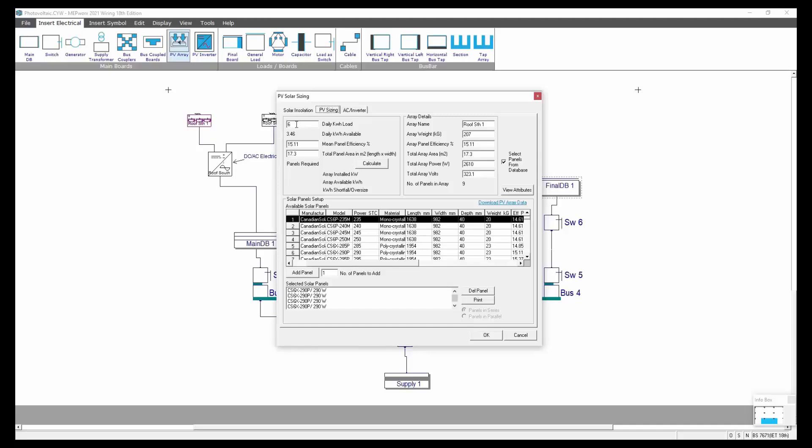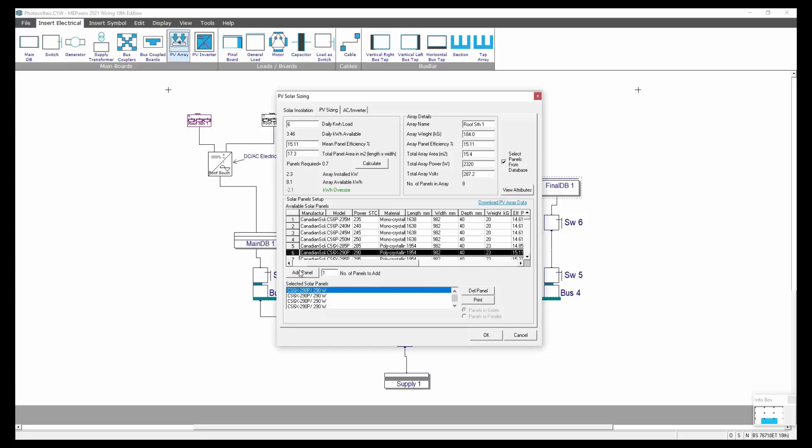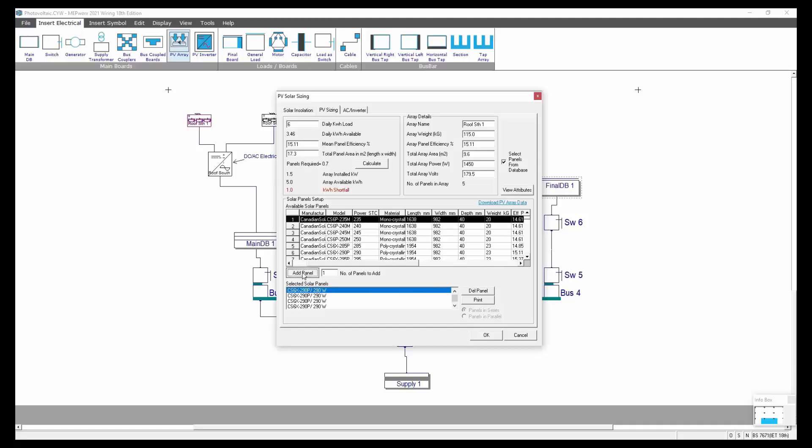When you go to the PV sizing tab, if you're servicing a daily load of so many kilowatt hours, you can put in a series of panels from this list. There's a database of panels which you can add to and take away from. For example if I was to delete a panel I can always then reinstate with another panel. You can see here the array available kilowatt hour load we're trying to service. If I was to remove this 290 and put in a 235 and add that panel in, you see I've got a bit of a shortfall there. The idea is to get your panels to at least meet the requirement to make sure that you can meet that demand.